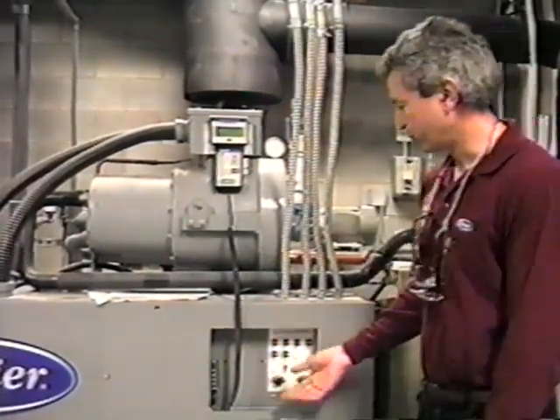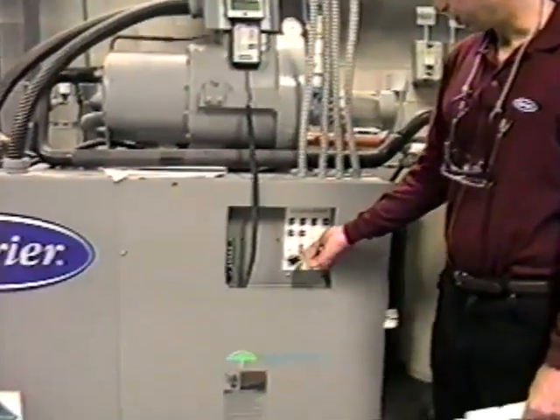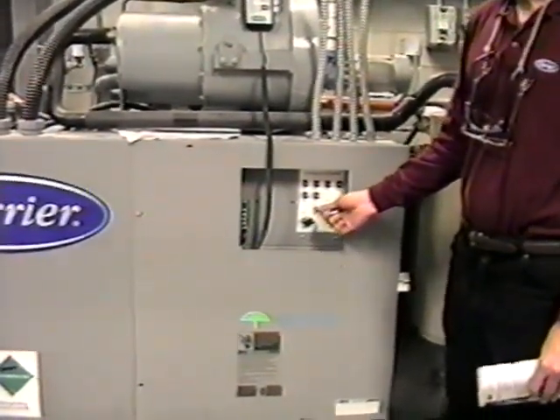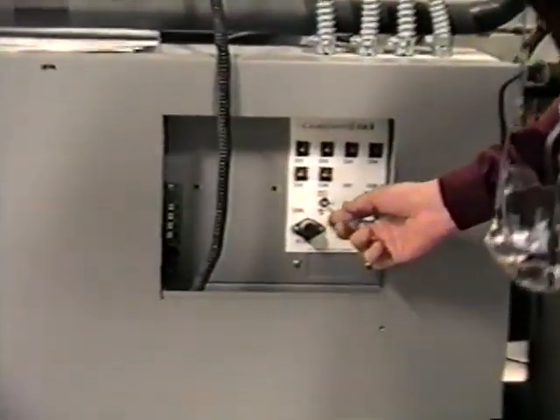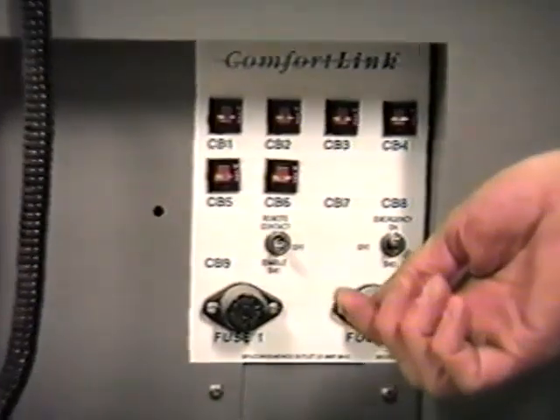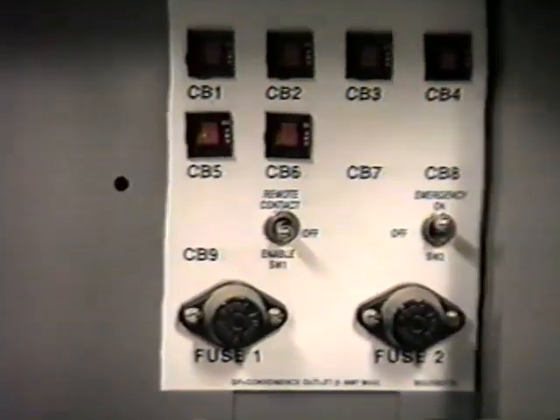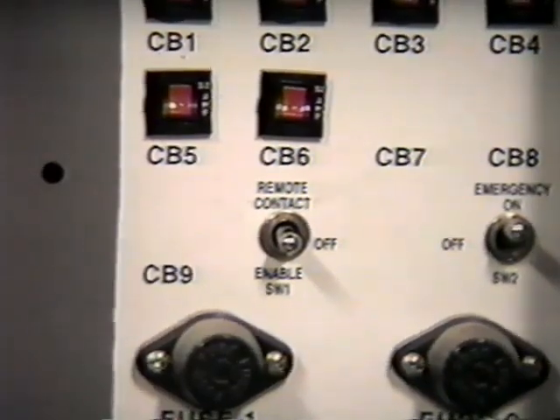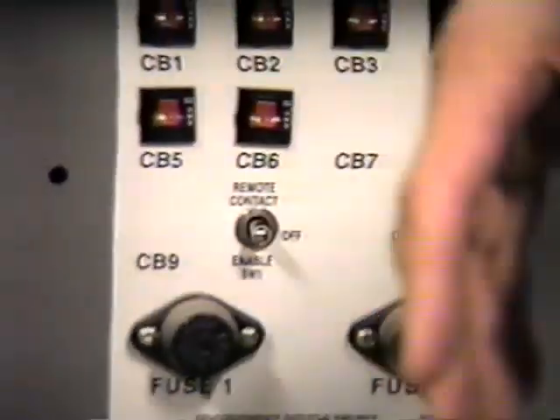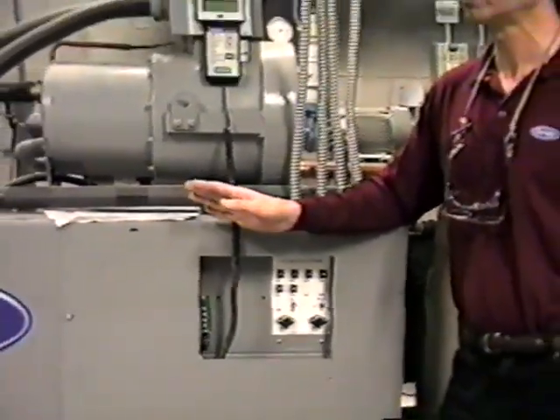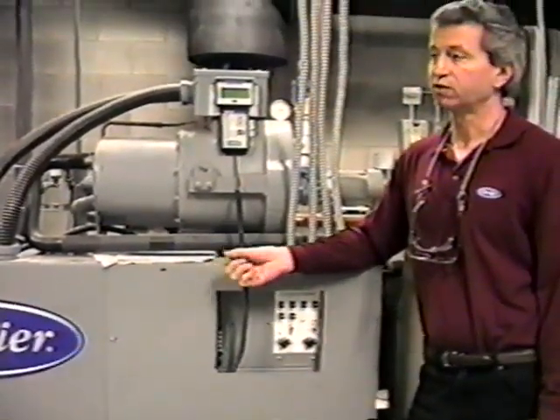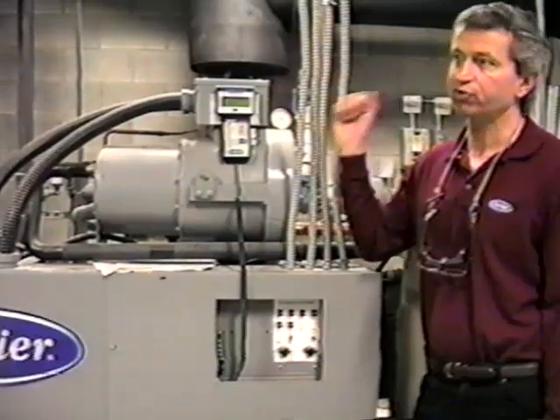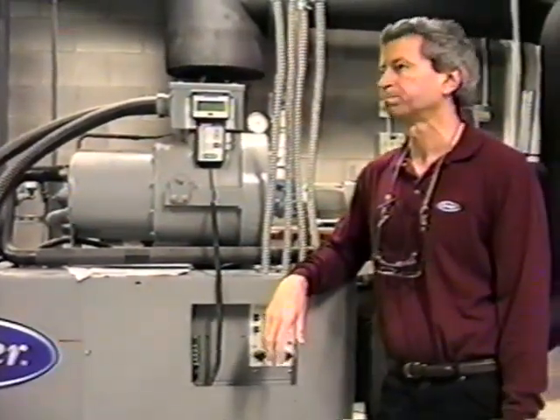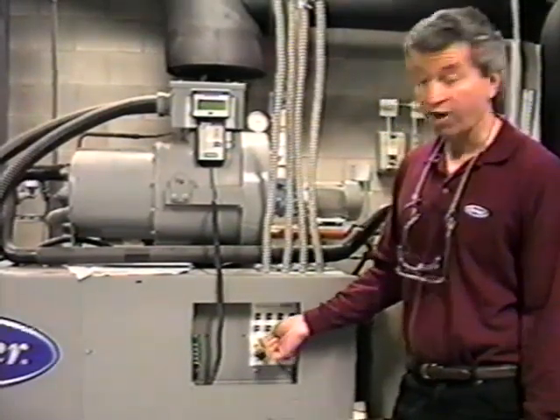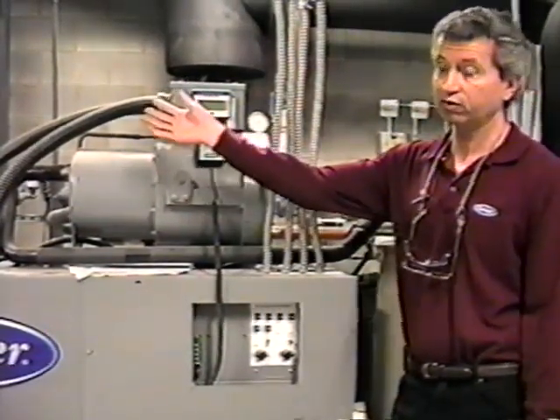Now onto this electromechanical portion of the panel, you'll see the one rocker switch. It has remote, contact, off, and enable. Essentially, you'll be operating in the remote contact mode, and what that does is it switches control over to the smart drive as far as starting and stopping. The smart drive will say I need cooling, it'll send a signal to the chiller to start, and then the chiller looks at your brine temperature and essentially controls capacity to that set point. Of course, in the off mode, regardless of what the smart drive is telling it to do, it's going to turn it off.